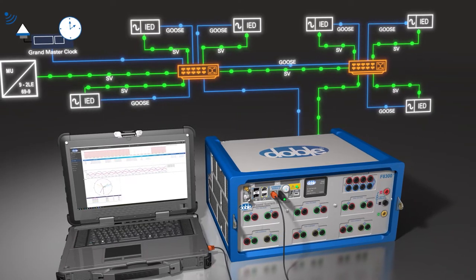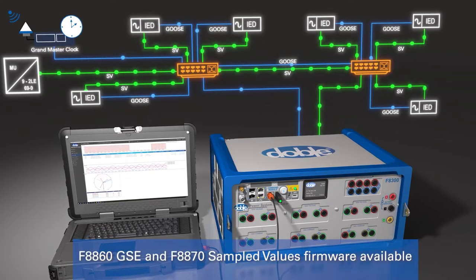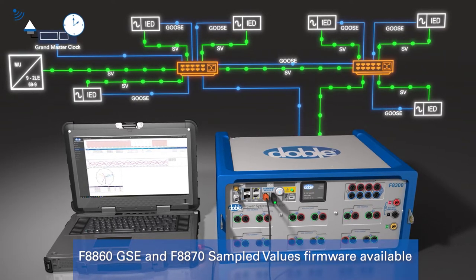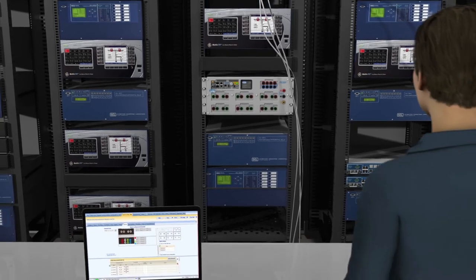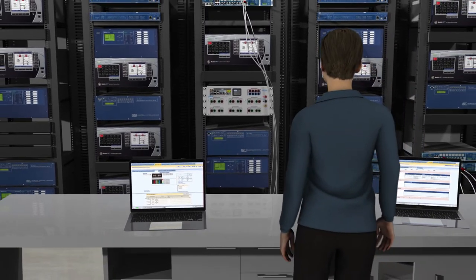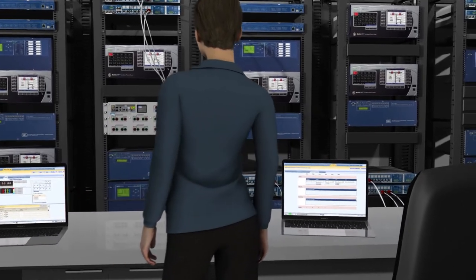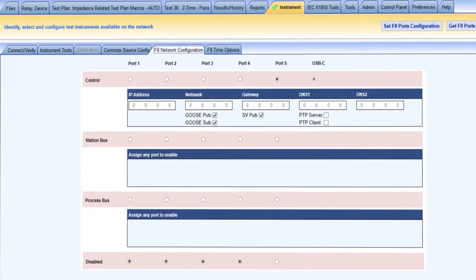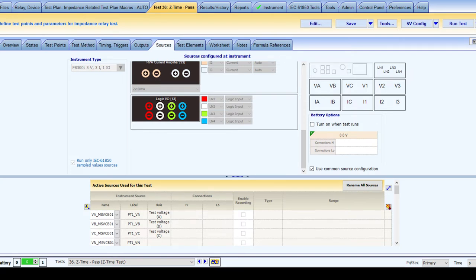Publish and subscribe to IEC 61850 GOOSE and Routable GOOSE communications. Publish IEC 61850-9-2LE and IEC 61869-9 sampled values. The command module isolates control, sampled values, GOOSE, and PTP networks and can separate or overlay the discrete signals according to port assignments configured in Protection Suite software.